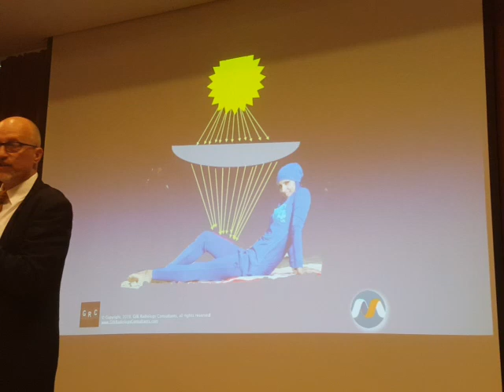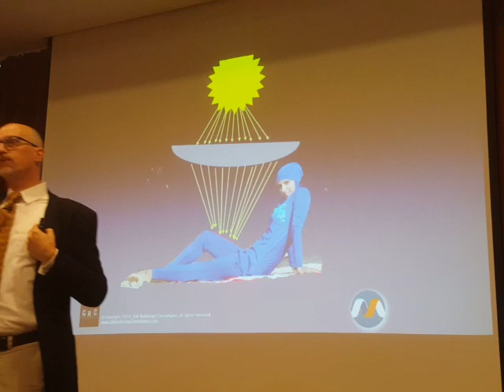For the proximity burns that we talked about, being too close to the transmit element, the RF power where it transmits is high, right? Because it gets weaker as it radiates out. So the closer we get to the point of transmission, it's higher, it's more focally concentrated. If we have an electrical conductor, an implant, a lead, a wire, something like that, that acts as an antenna, it absorbs that radio frequency energy with much greater facility than normal human tissue. And so what was supposed to be diffused throughout the body all of a sudden becomes concentrated into the pacemaker lead.